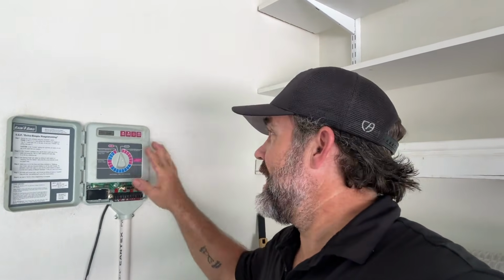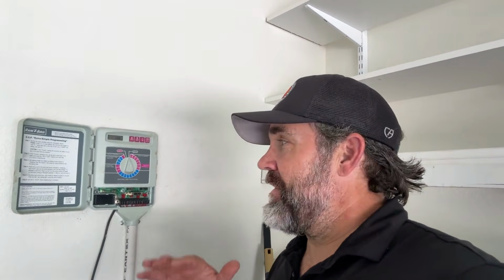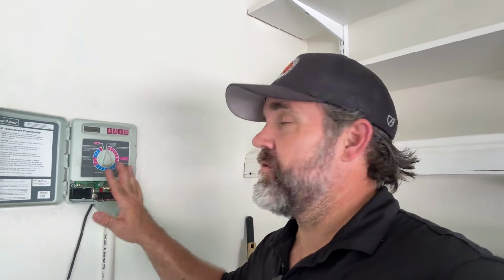Okay, so before we fire the system up, one thing I really stress to my inspectors, and something I've always liked to do, is take a picture of this control panel before I manipulate any of the controls or do anything. The reason is because you get into the inspection, especially on a system that's got 20 zones, and by the time you're done and you're walking around and you're wet and you're tired, you might forget what they had it on. Was it on? Was it off? So we always like to take a picture that shows the status before we touch anything, so we can always set it back. So let's get this system fired up, and we'll go check out some spray heads and drip lines.